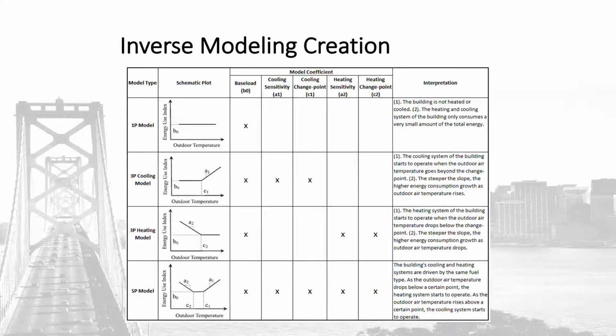The slope portion of the model, that coefficient, is a function of the building envelope, ventilation, infiltration air, and the efficiency of the heating or cooling system. In this case, because we're looking at outdoor air temperatures rising as we move further to the right of the graph, this is an indication of the level of efficiency of a cooling system. That point in the middle, C1, would be a break-even temperature point and is a function of the temperature set points in the building. Essentially, what Better is doing is creating these models, identifying these coefficients, isolating them, and benchmarking them against peers.